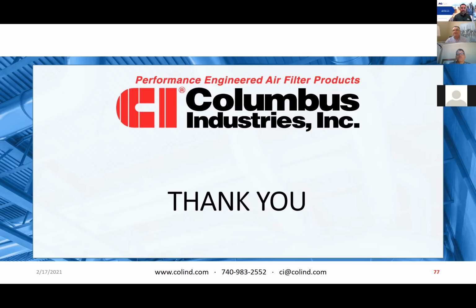I do have an application in cosmetics in France where they are using the PC plate, and they are using a more open PC plate, and behind they have a Supra 2 or a Supra 1 as a roll, not a pocket, because they didn't have the space. What's nice about it is that they have the roll on a metal frame that's on a rail that you can pull out. So they're using the PC plate as a buffer. It does capture a lot of that liquidy, runny stuff, and it protects the secondary filtration.